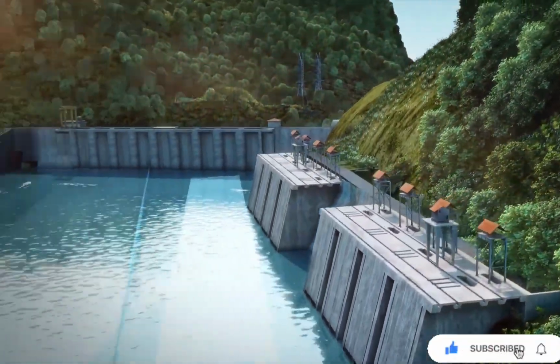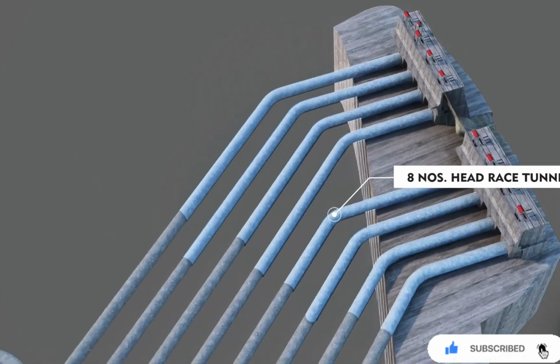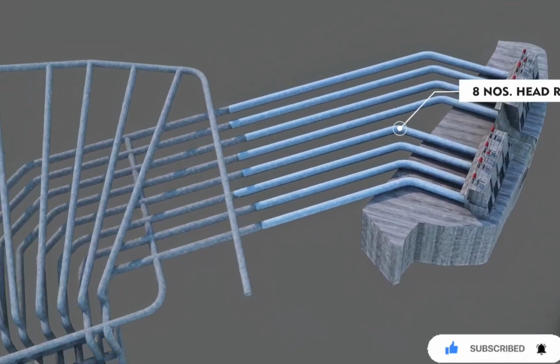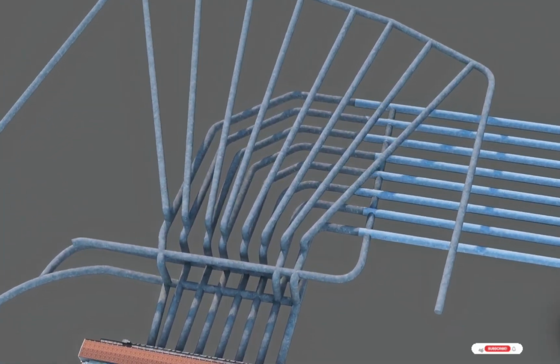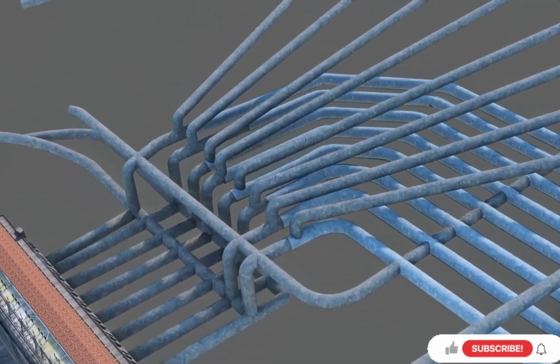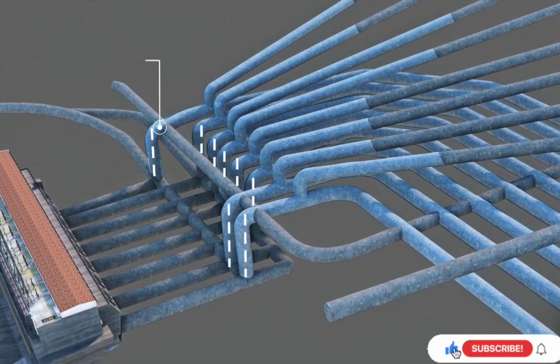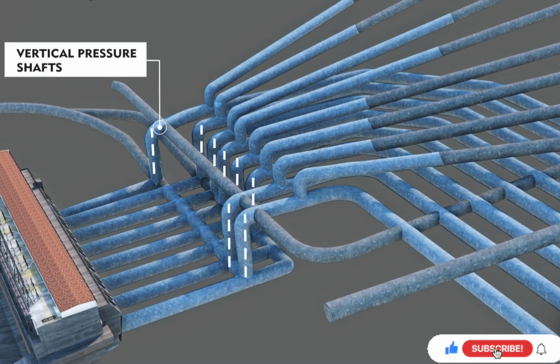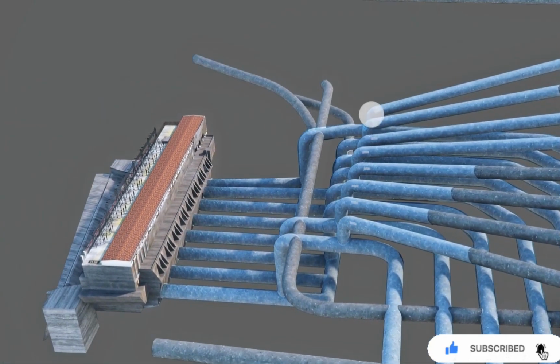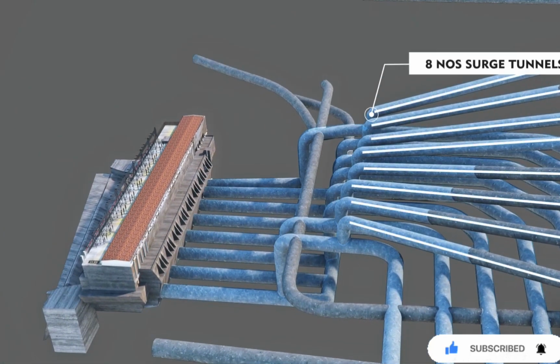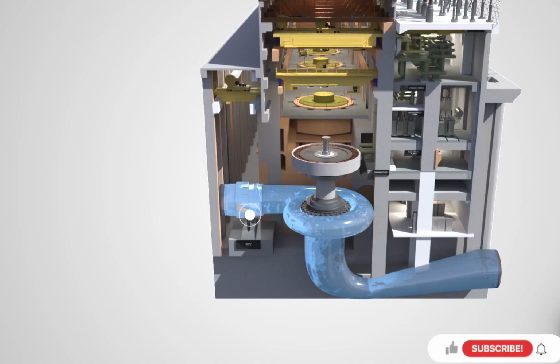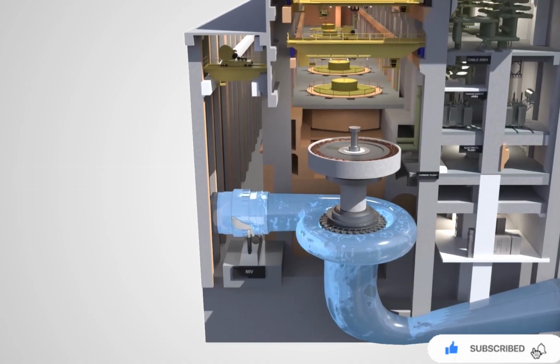Water is then conveyed through 8 9.5-meter diameter horseshoe-shaped head race tunnel to the powerhouse. Before entering the turbine, water is conveyed through independent vertical pressure shaft, where high head is generated to rotate 8 250 megawatt generators. 8 surge tunnels have been provided to protect the water conductor system from the water hammering effect. Along the penstock, a butterfly-type main inlet valve is installed to regulate the water inflow into the turbine during generation.